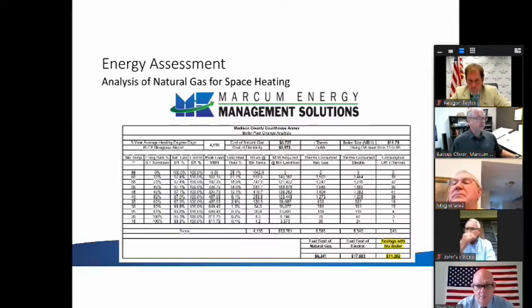Also, I had my engineers do a calculation on what we could expect if we changed the boilers from electric to natural gas. I've talked to your gas department, and we can install gas on this building. I would recommend gas for space heating and water heating, and also for the DOAS. In summary, the bottom right corner tells us that we could have a savings of $11,000 annually if we switched to natural gas. Natural gas costs less per therm than electricity, which is the reason for the difference. This is why I was surprised to find the building was all electric.